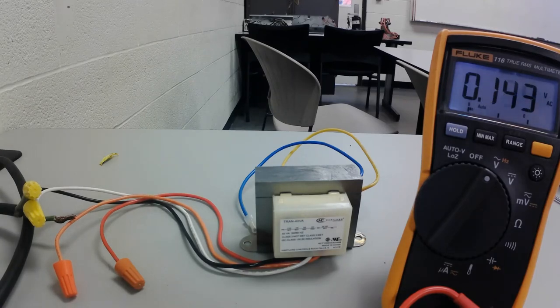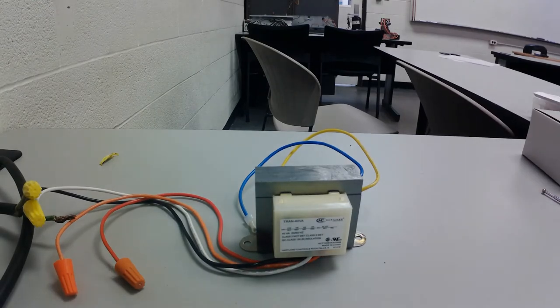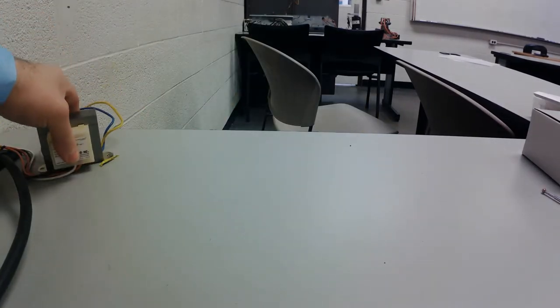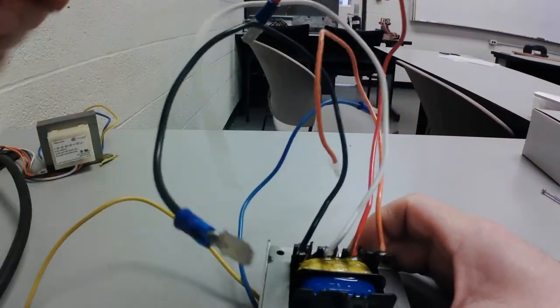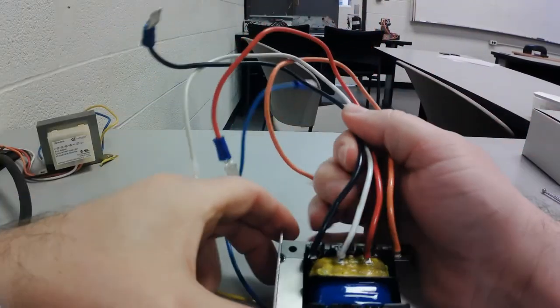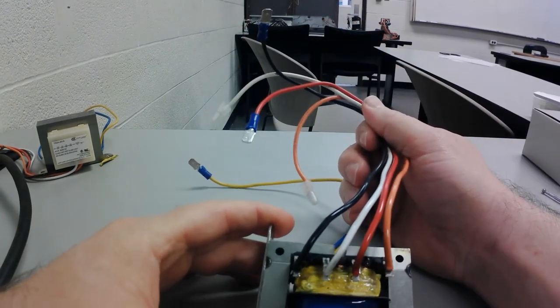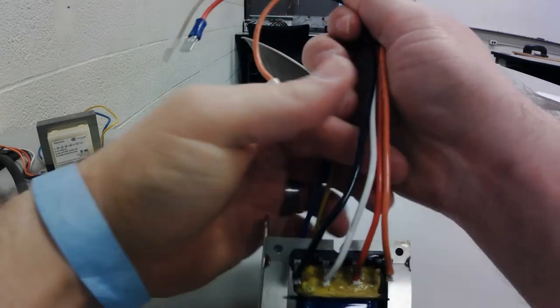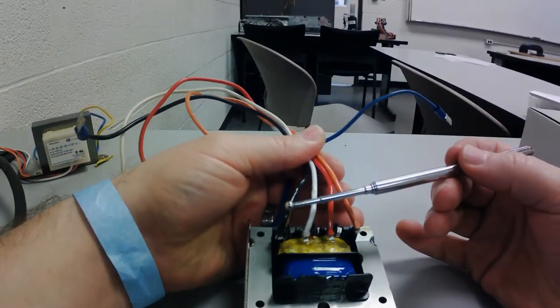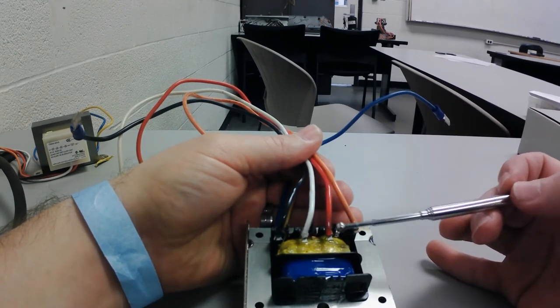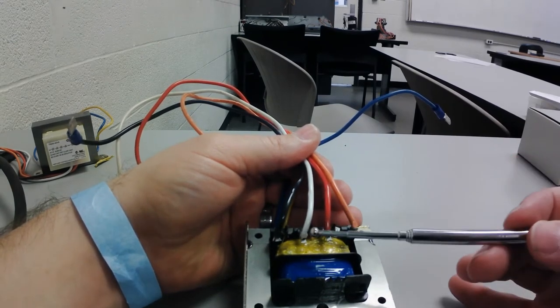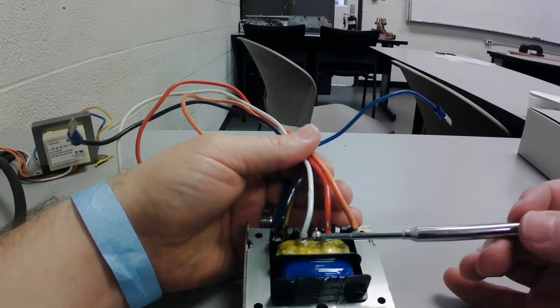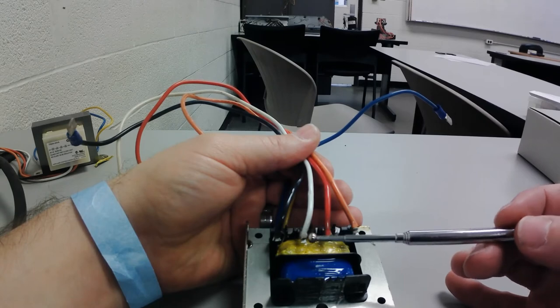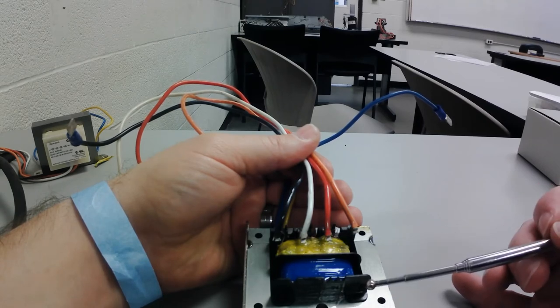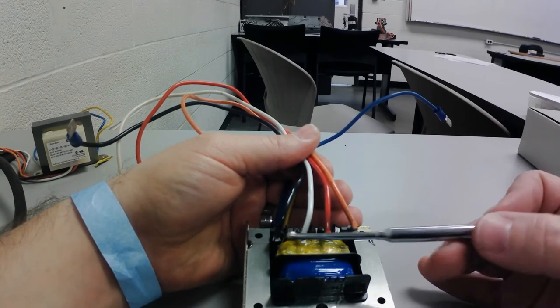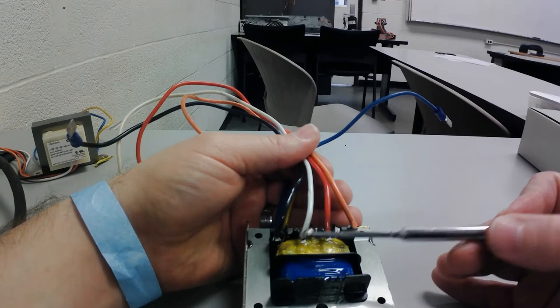Okay, let me bring back this other transformer. If you look at the way that this multi-tap transformer is made and pay attention to it, you'll realize that it's much like the three-speed motors that we have out in the field, the PSC motors. This black wire is always common. So we have 120 volts, then 208, and then 240. And these individual wires that are not the common, they are tapped into different portions of the primary winding. They're all connected. So you can't get away. If you put power on one, that's why there's power on the other one.